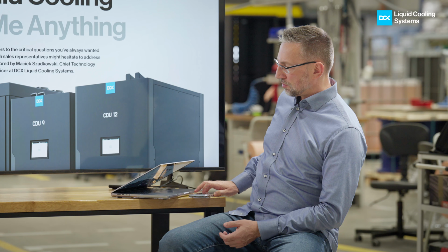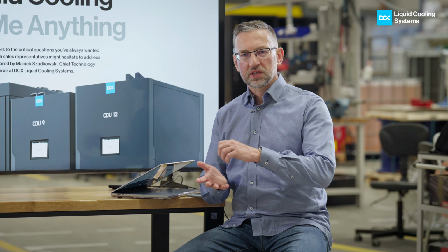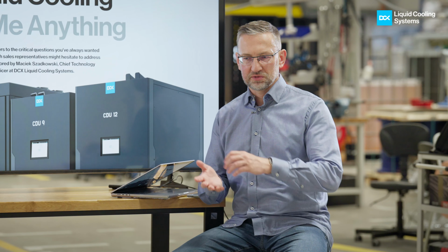The CDUs, or coolant distribution units, are sophisticated pump groups combined with a heat exchanger, which carefully regulate the flow rate and the temperature of the fluid which goes to the server racks in direct to chip cooling. That's the CDU, usually rack-based or skid-based. We need to control very carefully the inlet temperature to the processors, because if you get below the dew point, we'll get condensation and that will ruin your servers, because those components will start sweating, and we don't want that. That's why the CDU is so important for direct to chip cooling.